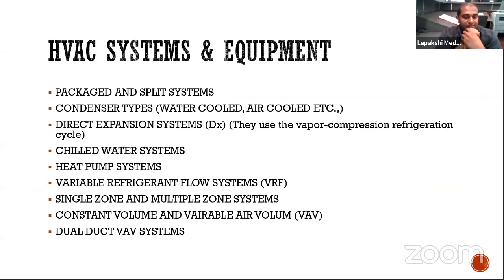Direct expansion systems are the widely used systems these days. Chilled water systems are used for institutional purposes, I would say. You don't use chilled water systems for medium range to small residential sectors. You use these things in industrial or institutional settings, where you might need a lot of chilled water to take the heat away from the conditioned spaces. Heat pump systems, which we just spoke about, are just a reverse of refrigeration or air conditioning systems. Next, VRF systems, also quite popular these days, which let you control both heating and cooling at the same time from the same condenser, from the same refrigerant. So that's very important, VRF systems.